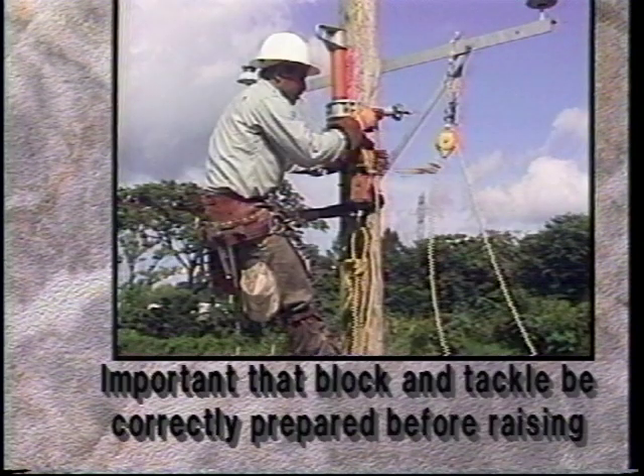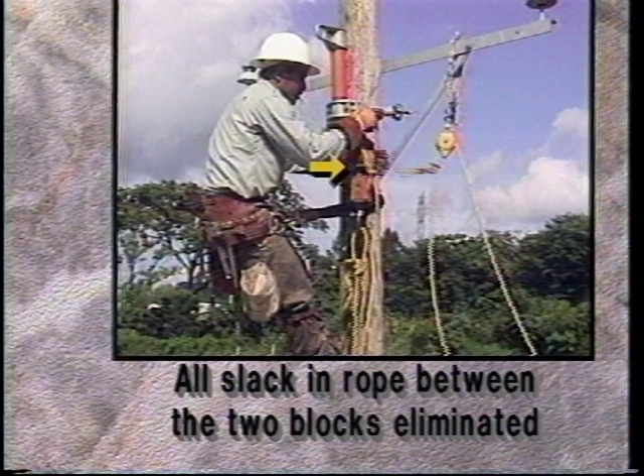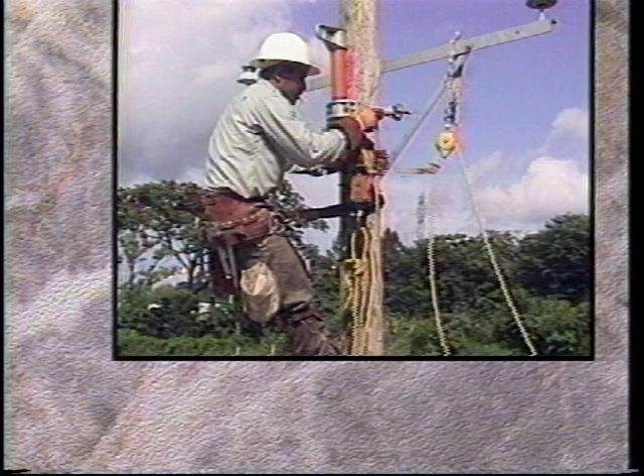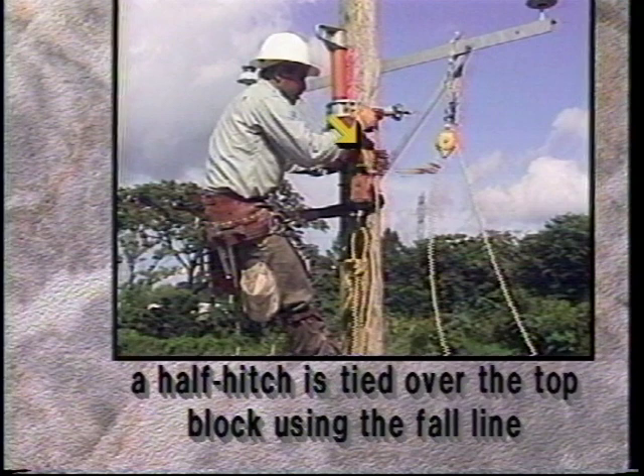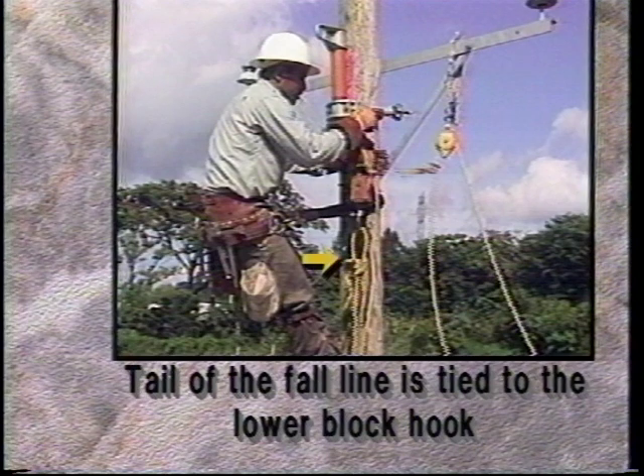It is important that the block and tackle be correctly prepared before raising it to the lineman. All slack in the rope between the two blocks should be eliminated, and a half hitch is tied over the top block using the fall line. This keeps the ropes from tangling and reduces the weight, allowing easier pole top installation. The tail of the fall line is tied to the lower block hook. This allows the block to be lowered by pulling the tail of the fall line once the block and tackle have been installed on the pole.